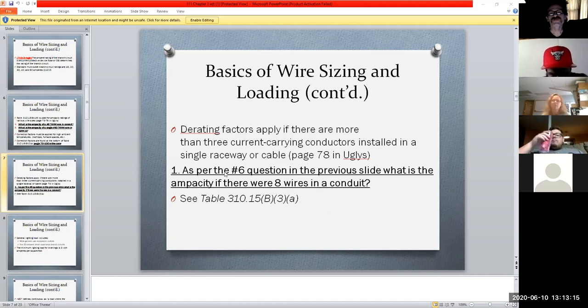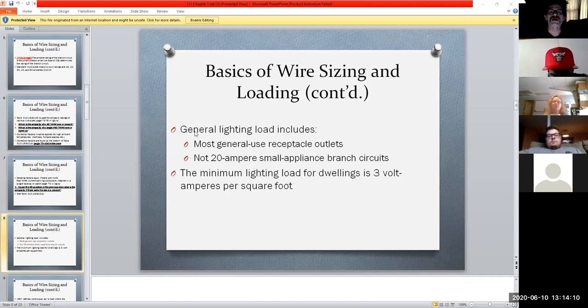So if we were to look up, let's say in the previous question, what our ampacity capabilities are if we have 8 wires in a given conduit. These tables and charts are listed, and we can look at what size conduit we're dealing with. If we have 1/2 inch, 3/4, or 1 inch, those are the 3 most common that we'll have within a house. There are exceptions to that, of course, but we'd be able to look it up and see. It's like, okay, what can we do here? Can we actually run 8 number 14s in this 3/4 EMT, and is that allowed? And again, it's going to be a heat factor. So if it says no, you're only allowed 7 wires in that, then we would have to size up to the next size of conduit in this case to allow more room for expansion for heat. Heat is our big thing we have to think about.